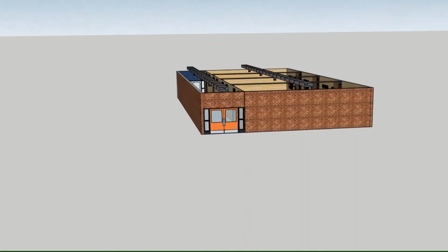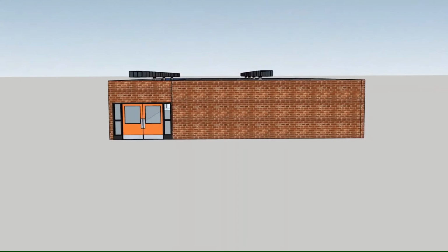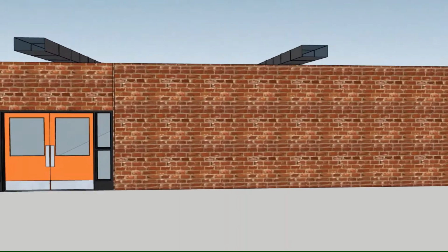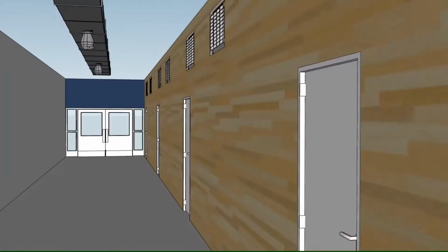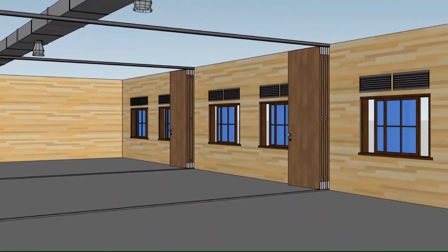The last type of ventilation is smart ventilation. Smart ventilation is a combination of system A and D. When there's a lot of wind outside, the system will switch to the grills from outside to ventilate. But in the case of no wind, the grills from outside will close and system D will be applied.